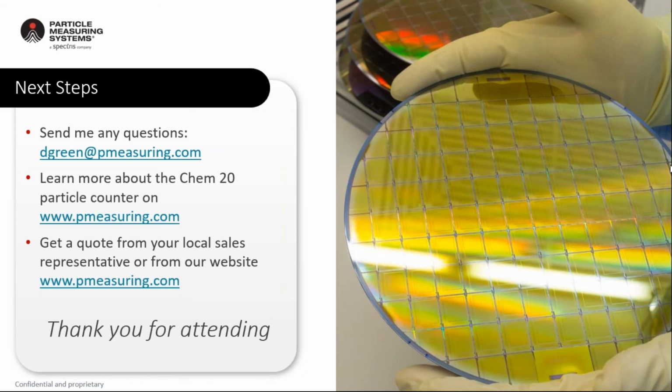And that gives you the ability to know that, between the storage tank and the point that it's being delivered to the fab, all of those portions of the tool are working, and the chemical going into the fab is as good as you would like it to be.